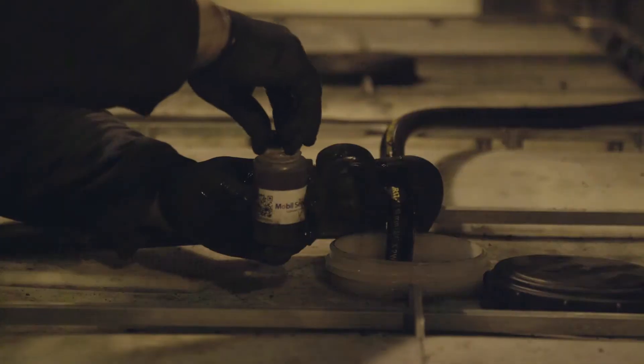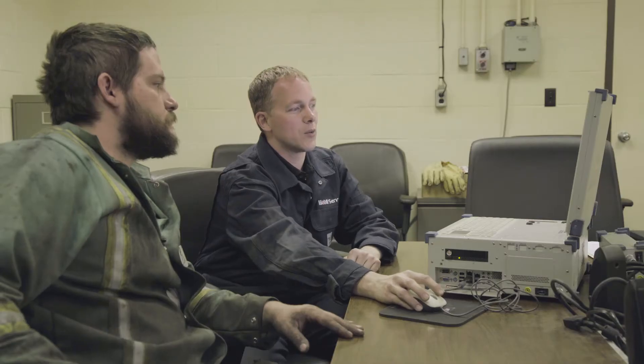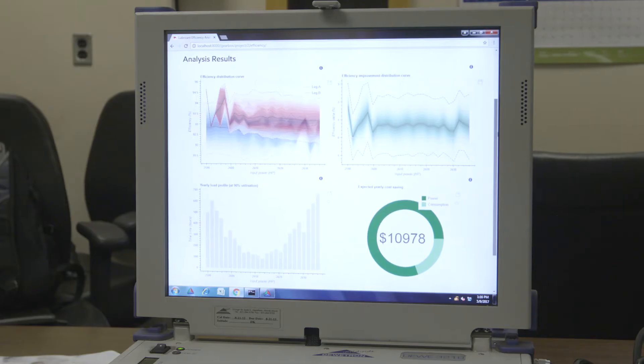After conducting the test, we are able to demonstrate a one percent efficiency gain. When we do our cost savings calculation, you get eighty-eight hundred dollars in savings just on that one gearbox per year, and then from an oil drain savings, twenty-one hundred and twenty-five dollars. We're looking at about eleven thousand dollars a year in savings per gearbox.